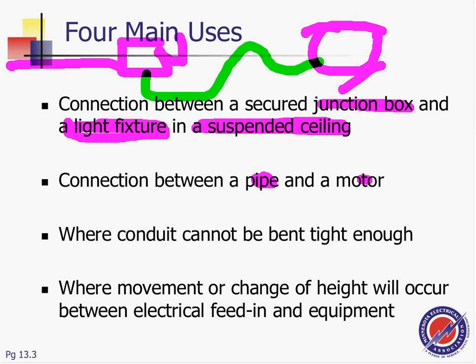Because if you tie your EMT to a rotating object, the whole wiring system might be vibrating in your building and making all these noises, which a lot of people don't like. Another one, it cannot be bent tight enough.